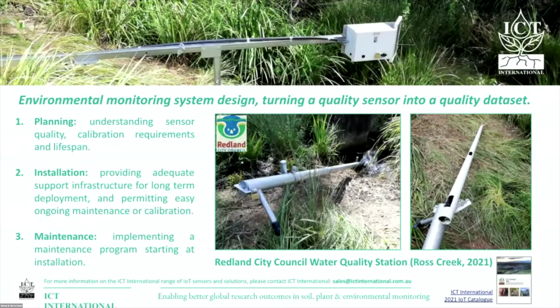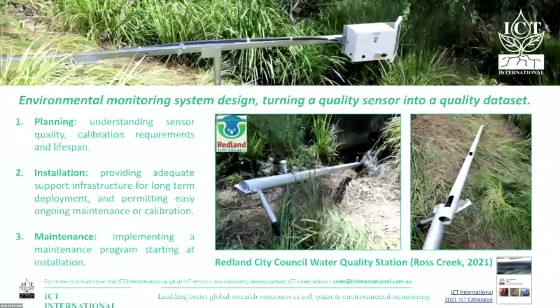The sensors, which aren't cheap, are housed in a steel-cased lockable enclosure, and they can be sleeved and pulled out from bank level to do your cleaning - which with any water quality sensor you'll have to do - and to do a calibration, which for this particular sample of sensors is generally every 6 to 12 months. That's something you need to consider at the outset and plan your installation and monitoring program around those constraints and risks.